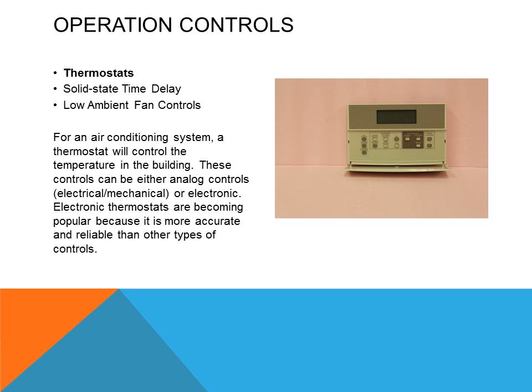For an air conditioning system, a thermostat will control the temperature in the building. These controls can be either analog, which is electromechanical, or electronic. Electronic thermostats are becoming popular because they are more accurate and reliable. One reason room thermostats are becoming digital is that they are not sensitive to levelness. The old type of thermostats that used mercury had to be perfectly level on the wall, and if they weren't, they were out of calibration.